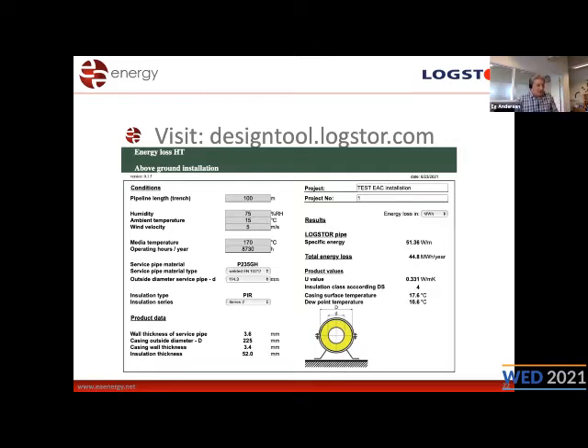This is the one. Logstor, they have this calculation tool online where you could go in and see design tool logstor.com, where you can go and make your own examples on energy loss. But I've put in some data up front where we say we have 100 meters of pipes, humidity 75, ambient temperature 15, wind velocity, very important to put in 5 meters a second. Then you will have 170 degrees Celsius, and you run almost all year. You should have said 8,760. So we have 30 hours for maintenance. No, so that's a full year.